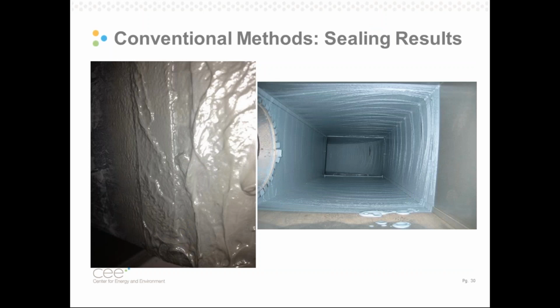This is what sealing looks like using conventional methods. On the left, we have externally sprayed-on mastic totally encapsulating a transverse joint. That is a good seal. On the right, we have the results of the robot that traversed this duct and sealed the joints and seams and the branch takeoff all along this ductwork. In both of these cases, we have excellent seals. We may quibble about the efficiency of using this much sealant, but at the end of the day, this ductwork is very tight.